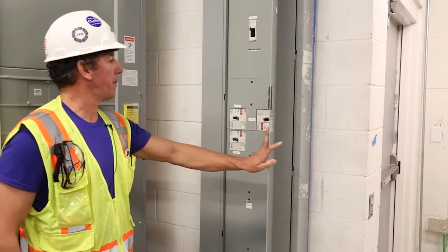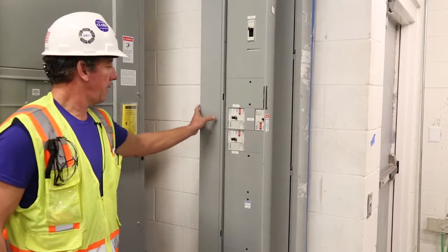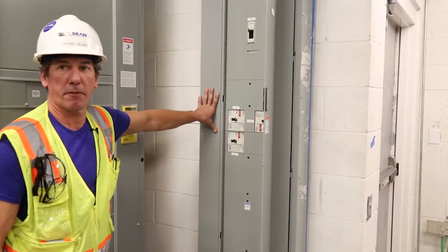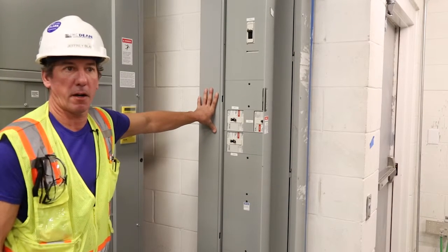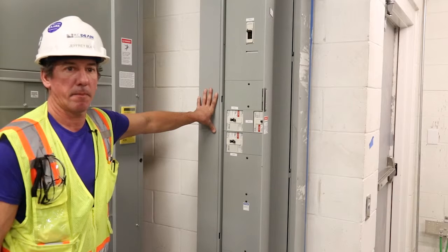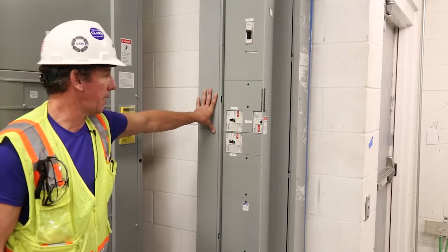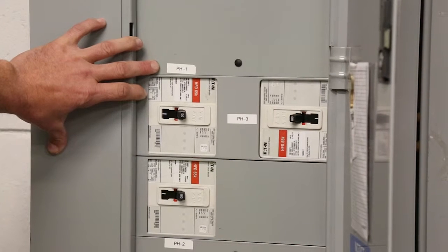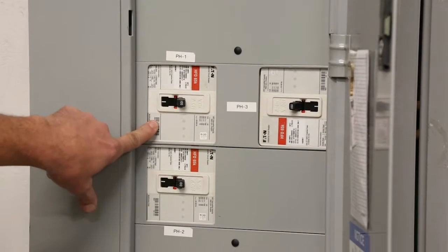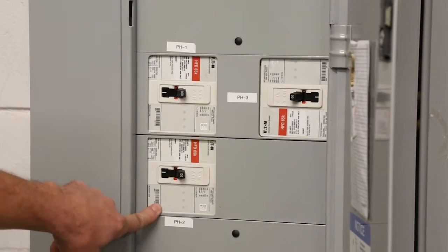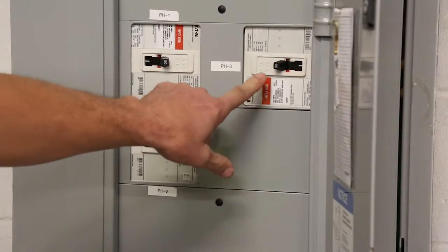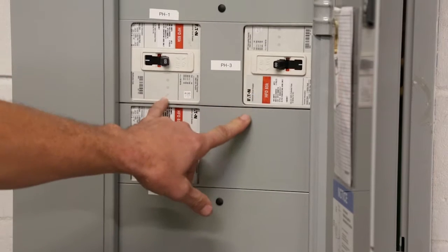All right, this is panel MDP. MDP's primary function is the parking garage. This panel feeds everything in the parking garage, all your lighting, receps, air fans, anything to do with the parking garage. Okay, you have electrical room on 100. This 100 amp breaker feeds it. You have an electrical room on 200 and one on 300 as well.